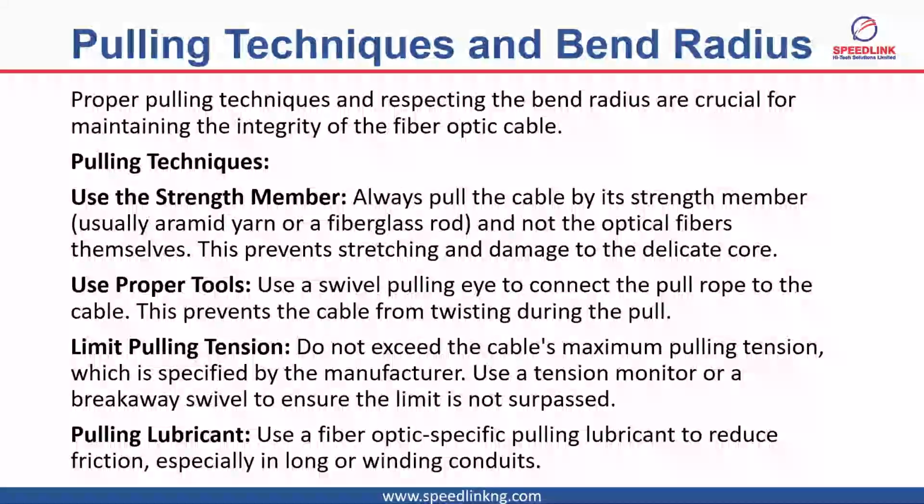So you have to limit the maximum pulling tension, which is specified by the manufacturer. You have to stay below that limit. Use a tension monitor or a breakaway swivel to ensure the limit is not surpassed.